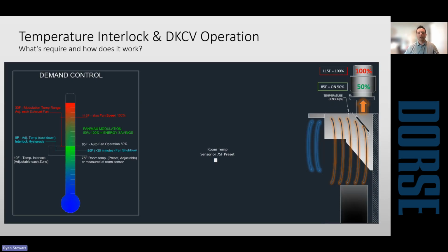So how it works: there are two options. You have a room temperature sensor that's measuring actual room temperature, or in cases where a kitchen may not be well conditioned, you can use a preset temperature. So based on a 75-degree room temp or preset, once the appliances turn on and produce more than a 10-degree rise in temperature, it activates the system and brings it on at its 50% airflow.